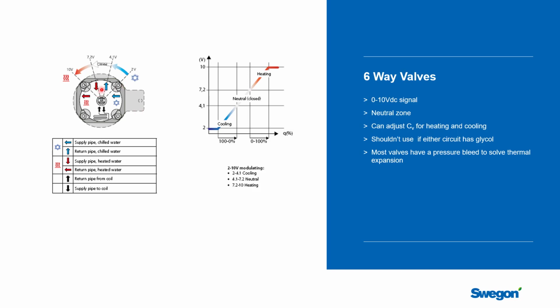Once you close off one of these loops, if you go from cooling to heating, there's no expansion tank on that cooling loop. So as that water warms up, sitting idle in the pipe, it's going to expand and put pressure on it. And so internally to the valve, you want to be able to bleed that pressure off and not have any issues with expansion cracking a joint in the piping system. So that's all looked after inside these valves.